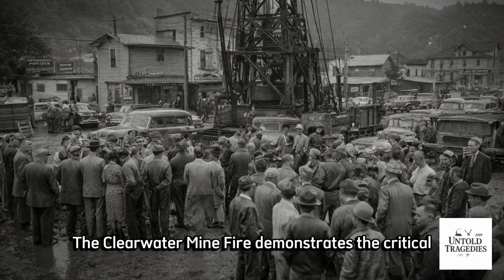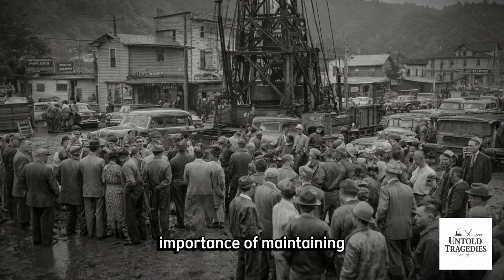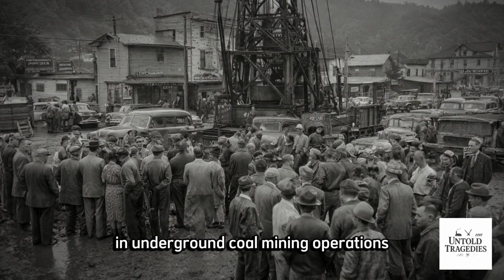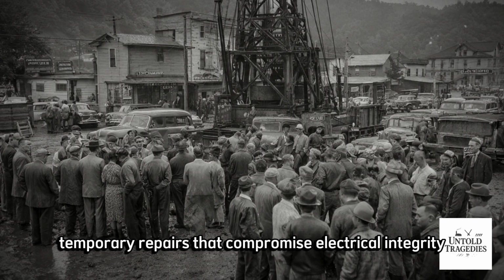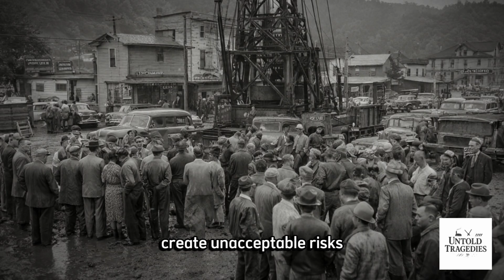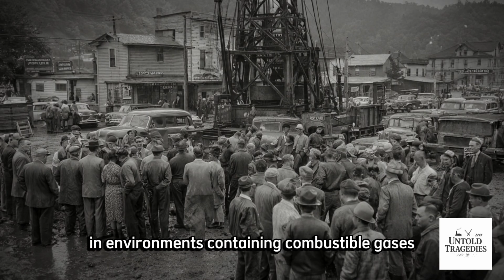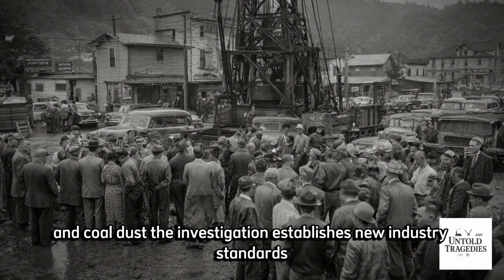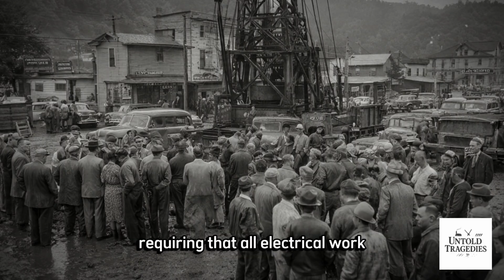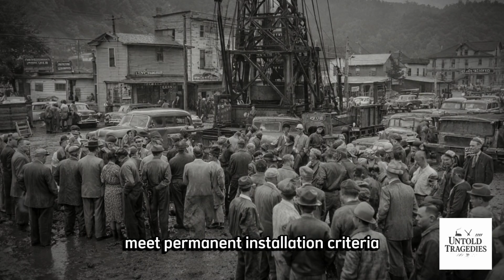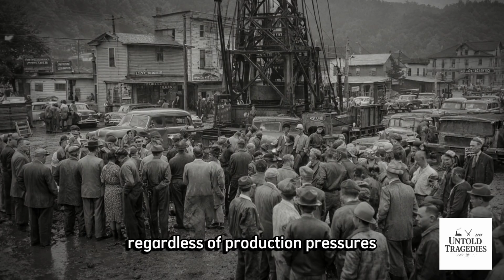The Clearwater Mine fire demonstrates the critical importance of maintaining electrical safety systems in underground coal mining operations. Temporary repairs that compromise electrical integrity create unacceptable risks in environments containing combustible gases and coal dust. The investigation establishes new industry standards requiring that all electrical work meet permanent installation criteria regardless of production pressures.